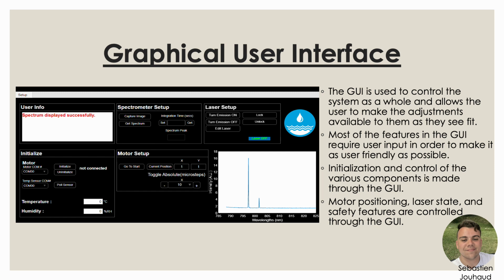Once you have that image saved, you can hit get spectrum, go back to the image you just took, select it, and once you hit open, the graph at the bottom will update and some kind of Raman spectroscopy intensity will appear there. For a different spectrometer, you can also adjust the integration time. You type in the value you would like in seconds underneath the integration time and hit set, and that's it. As for the laser setup, the turn emission on and off is also for a different laser that might be implemented at a later date.